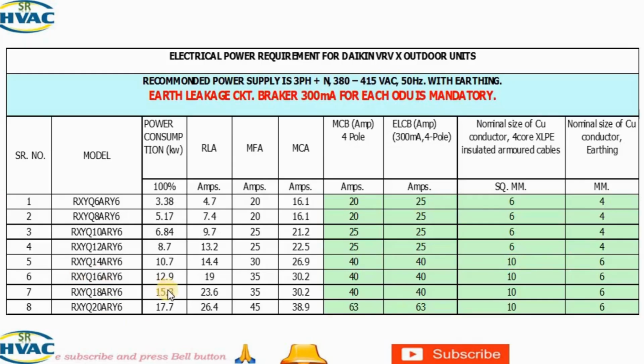For the 16 HP, you can see 12.9 kilowatt. You need a MCB of 40 and 40 for the same ELCB, and 10 square mm and 6 square mm. We'll see now 18 will remain the same, and 20 will be RXYQ 20 ARY6. It will be 17.7 kilowatt. The MCB will be 63, and the ELCB will be 63, and you require a 10 square mm 4-core cable, and the earthing will be 6 mm copper earthing. These are the basic details of the Daikin VRV X outdoor unit. You have to follow this one.